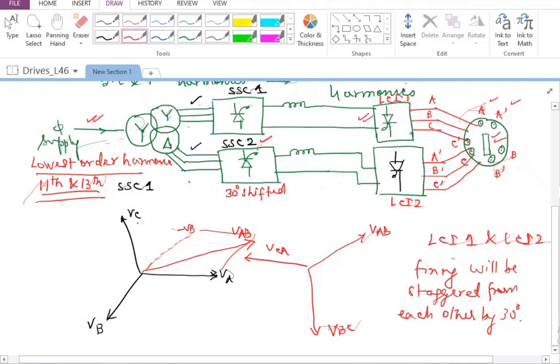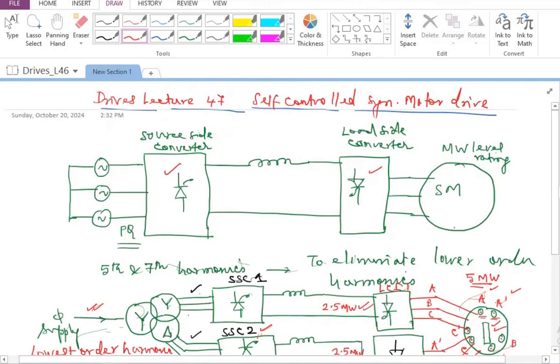from the input side. And each of the converter rating can be only half the machine rating. So if the machine is rated for, let us say, 5 megawatts or something, each of these converters will be rated only for about 2.5 megawatt, which is more manageable compared to 5 megawatt. And even the power that is being pumped into the machine will be shared between the two stator windings we have got. So this is a very, very common arrangement. This kind of 12 pulse converter is a very common arrangement in many of the synchronous machines, which are supposed to be much larger in terms of power rating.